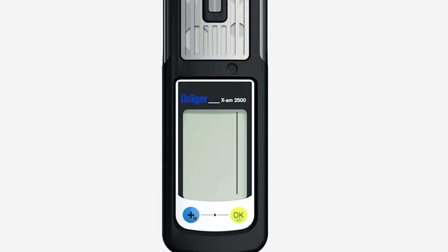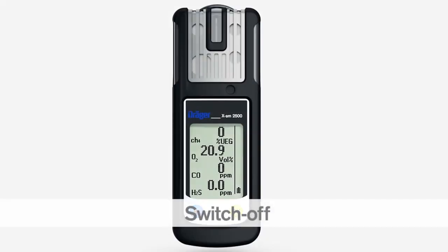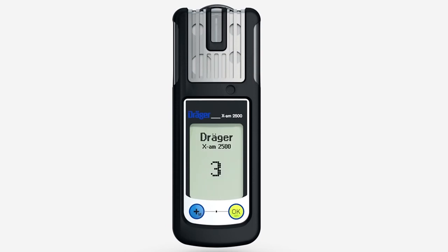The self-test screen shows the installed software version, the special symbols, the number of days until calibration is next due, the alarm thresholds, and the TWA and STEL alarm thresholds. To switch off the Dräger X-am 2500, press and hold the OK key and the plus key together for three seconds. The visual alarm flashes and the audible alarm beeps to indicate that the shutdown sequence is complete.